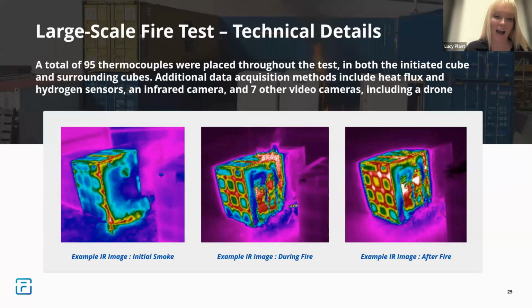You also want to look at the distribution of that heat. That helps us understand if the fire rating of the walls and the amount of insulation we have within our containers is sufficient, or if we need to change that. You do see, for example, as we move in cell energy density, from a 200 series to a 300 series to a 500 series cell, some of those, depending on the chemistry and the cell manufacturer, will burn hotter than others. We need to understand that so we can make sure we have the correct level of insulation in there, and we're not seeing that transfer across the site.